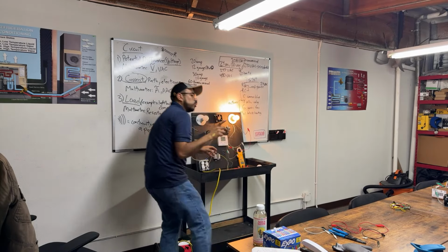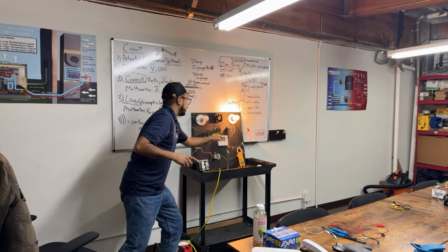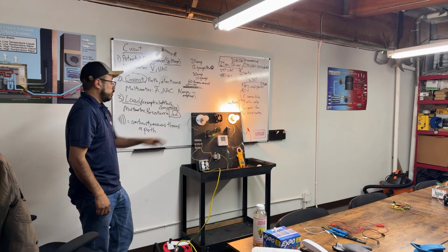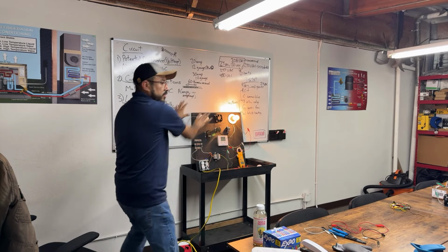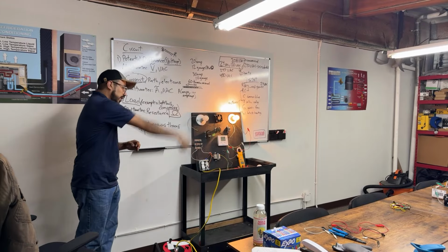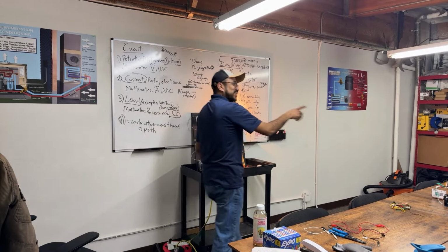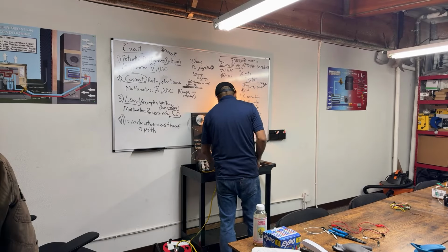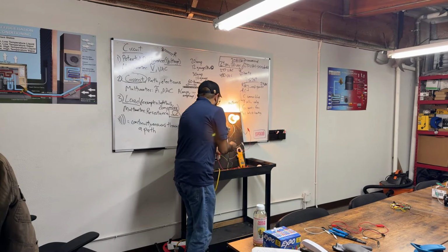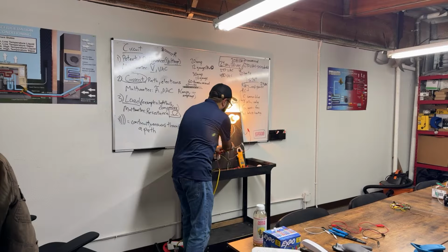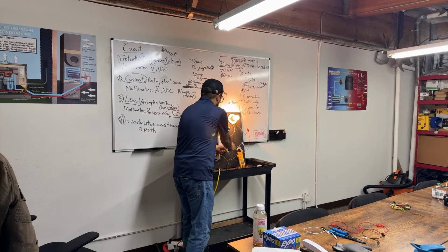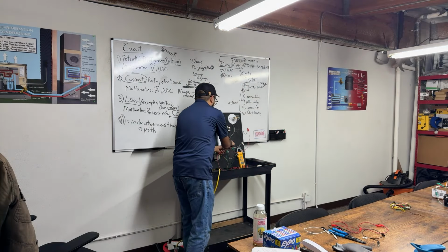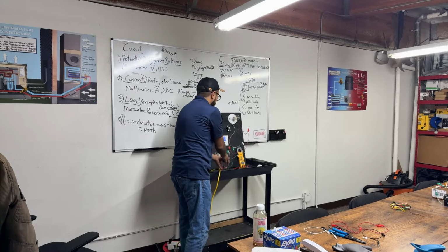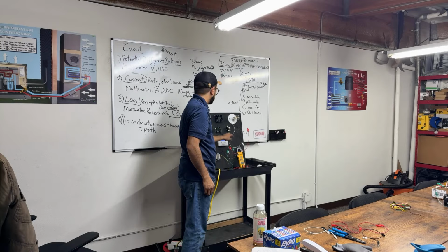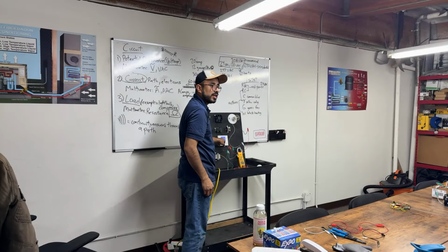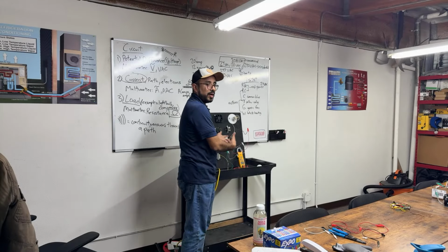What do you think my voltage would be between common and my yellow wire? Right now there's a call for cooling, right? 24? Good job, Todd. Andrew got it right. So look, guys, common and yellow, I'm getting 24 volts. When I don't have a call for anything, it's 0, because yellow now lost the 24 volts since I don't have a call for cooling. It's not getting the 24 volts from my red wire, my power.